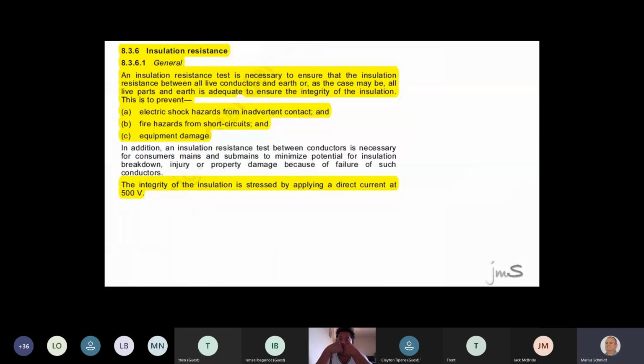Have you guys ever heard about the insulation resistance test? Now, before I do this test, can you take an insulation resistance tester and measure with voltage on the installation, or must the installation be off? Off, because 500 volts DC and 230 volts AC, apparently they don't like to talk to each other. Something's gonna go. What's gonna do that? The voltage or your meter? Correct. A lot of the meters have a fuse in, and the fuse will pop. Imagine you borrow your boss's $2,500 Fluke. You know, that big thing. And you plug it in and it goes poof. You know what you're going to say? Ish. So you're going to switch it off, put it back, and say, I haven't touched it.